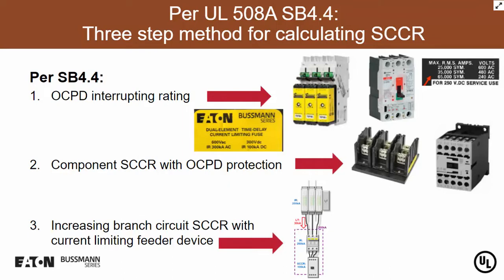There are 3 steps. Step number 1, and as you can see, we have fuses and breakers. So you've got to take a look at the overcurrent protective devices in the panel, on the power circuit. We look at all of the overcurrent protective devices and we look at the smallest, or the lowest, interrupting rating of those devices. And that is going to be step 1's answer. So for instance, if we have all fuses in the industrial control panel or machine, most fuses in there are going to be 200,000 amps. So the machine's lowest rating is going to be 200,000.